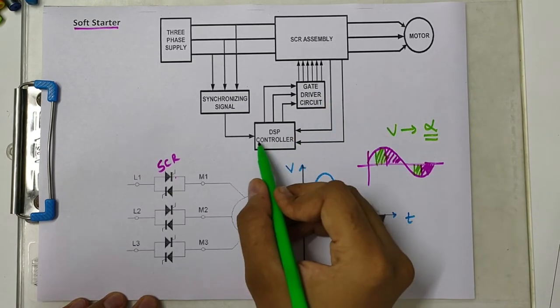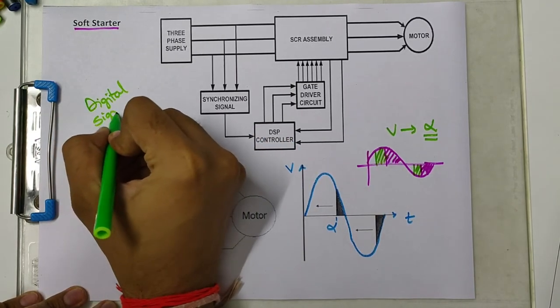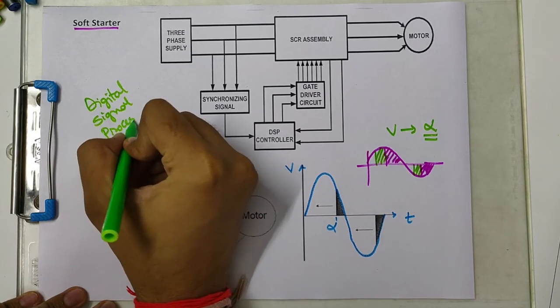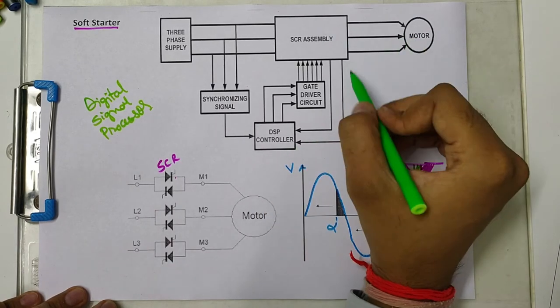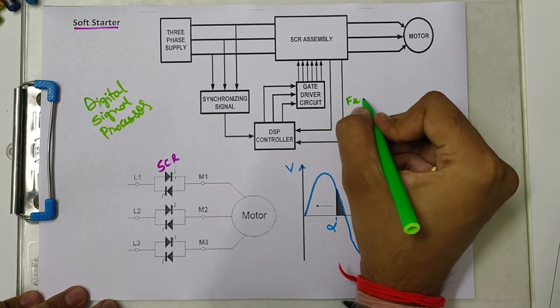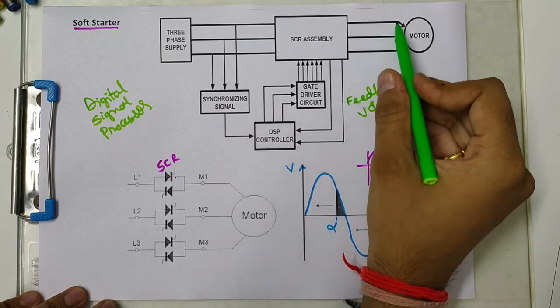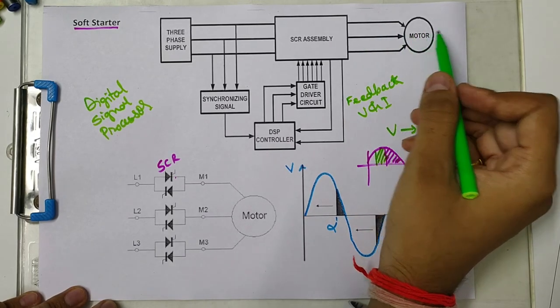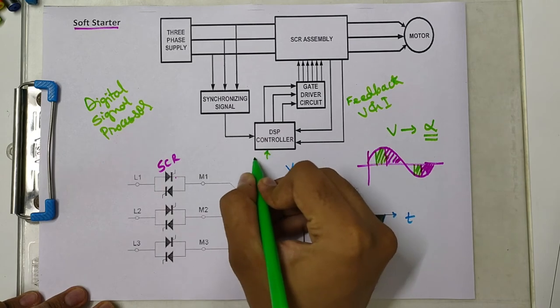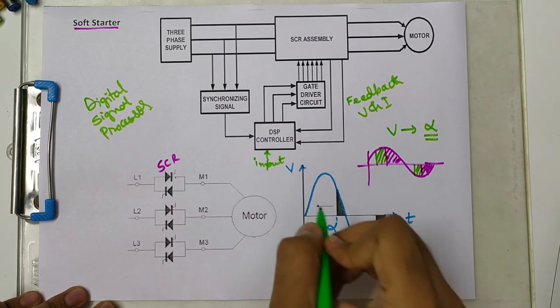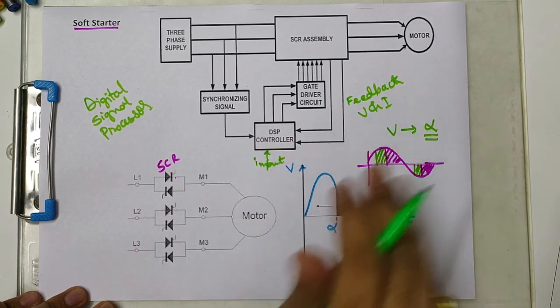The gate driver circuit receives information from the Digital Signal Processor (DSP), which is a very fast microcomputer or microcontroller. It reads the values of voltage and current - this is the feedback of V and I. It measures the voltage and current going into the motor and takes the synchronizing signal from the input supply.